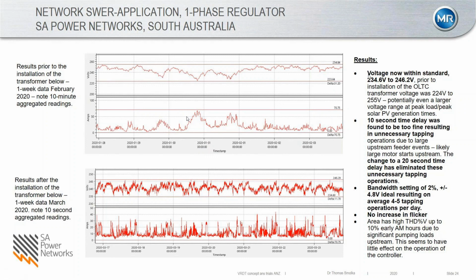Regarding some settings, of course they have not integrated the device into SCADA. So they just have a basic relay where we can do some settings, play with some time delay. And the 10-second time delay they found a little bit too fine, so they modified this to 20 seconds, which finally helped them to see only 4 or 5 tappings during the day.